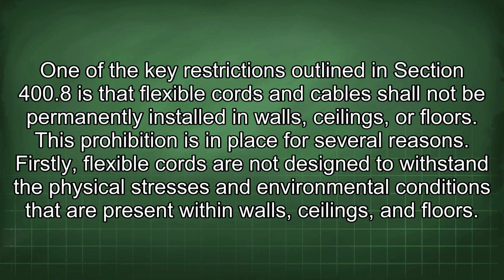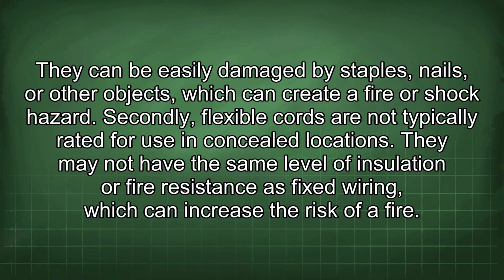This prohibition is in place for several reasons. Firstly, flexible cords are not designed to withstand the physical stresses and environmental conditions that are present within walls, ceilings, and floors. They can be easily damaged by staples, nails, or other objects, which can create a fire or shock hazard. Secondly, flexible cords are not typically rated for use in concealed locations.